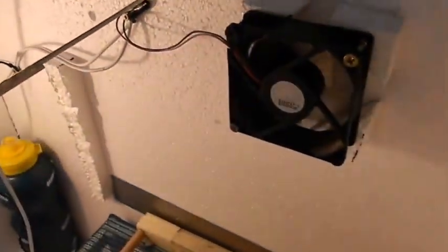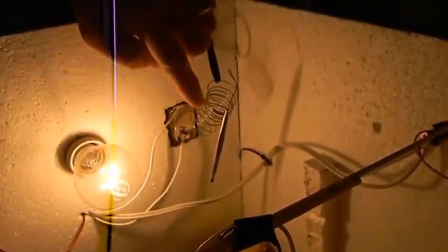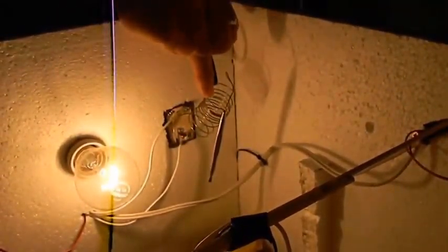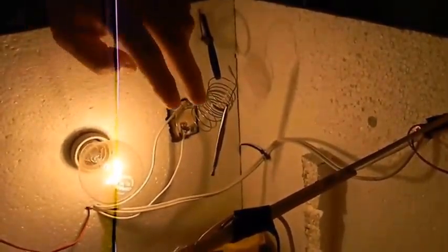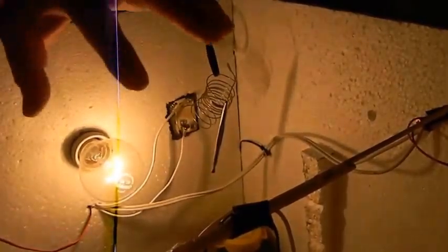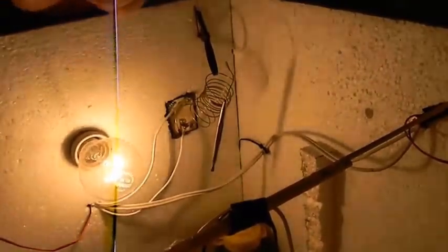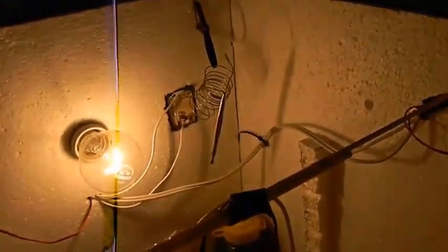To make sure that there's good distribution of heat in the incubator, it's quite important to have the energy source, your heat source here, and your thermometer very close by. Because if it's far apart you get very large fluctuations in the temperature inside the incubator. You need that switching on and off of the light to happen relatively quickly. It takes about a minute or so for that cycle to happen.